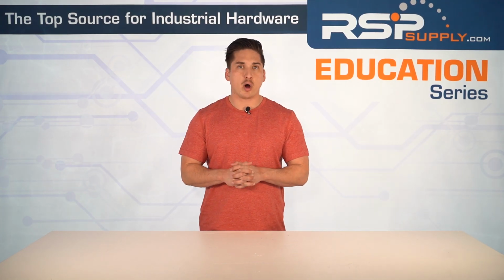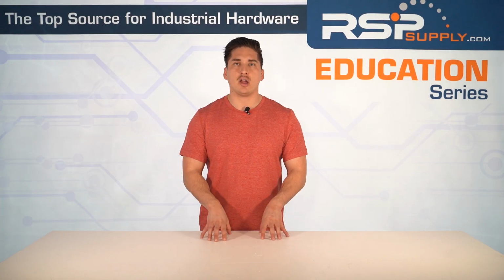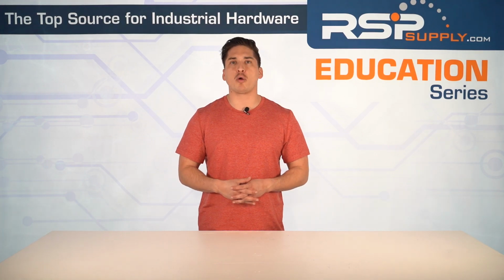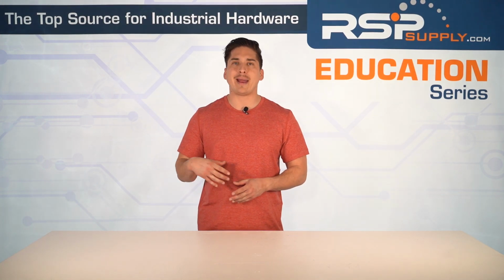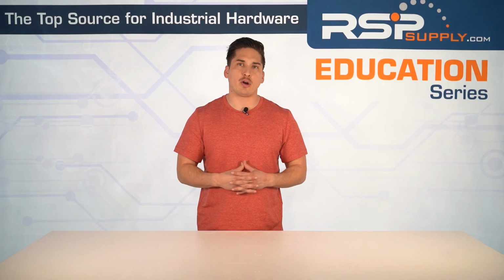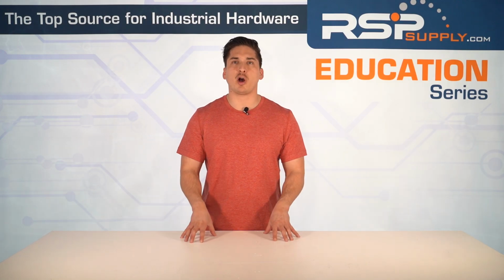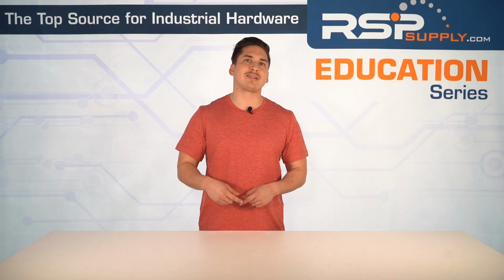In industrial automation, protecting motors goes beyond just using a standard circuit breaker. Motors have unique electrical demands, from high inrush currents to continuous load variations, and this requires specialized protection. In this video, we're going to break down motor protection circuit breakers, or MPCBs, how they prevent overloads, short circuits, and motor burnout.